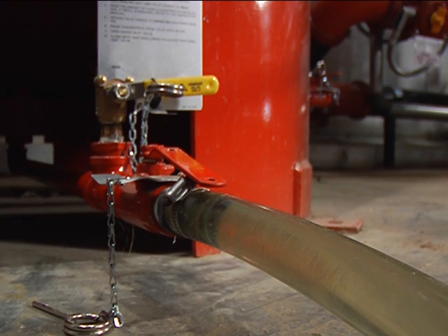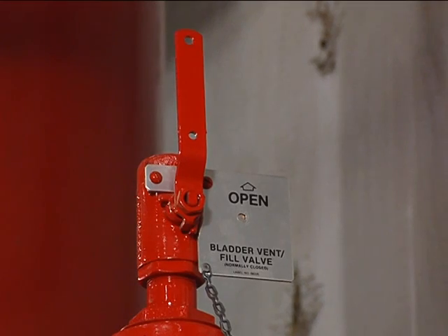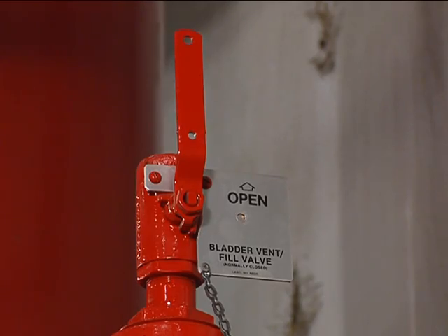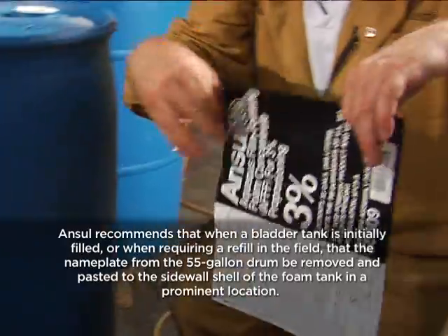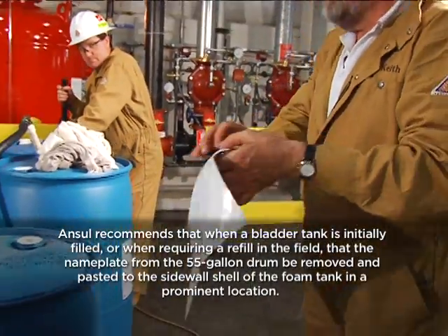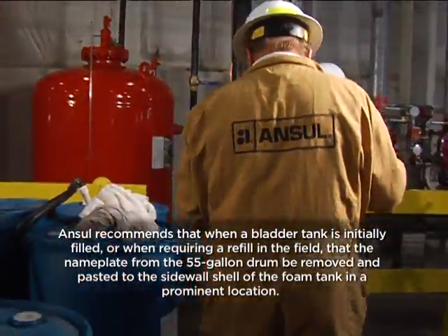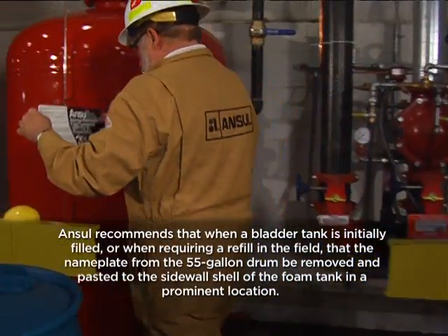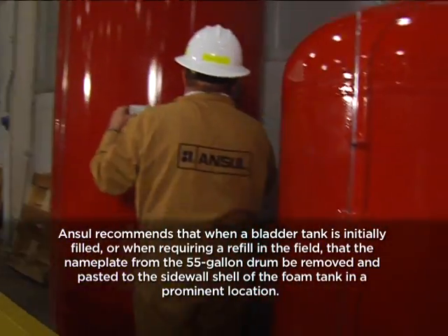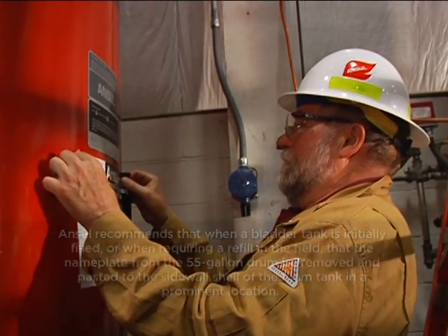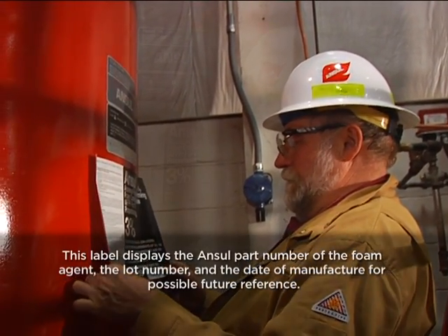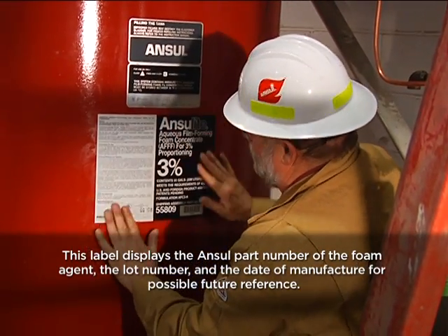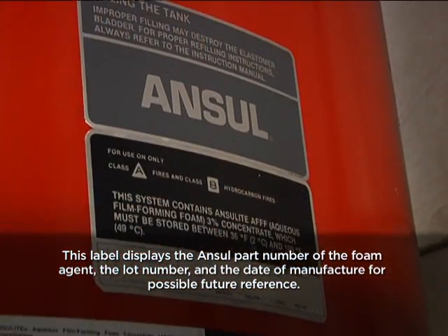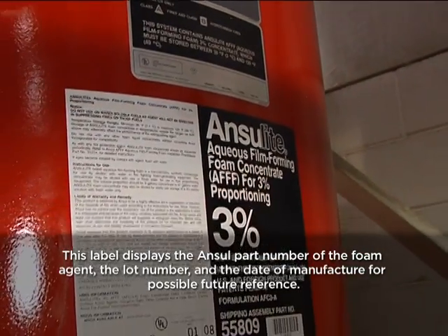At this point, the only valves that should be open are the pump valve, the bladder drain fill valve, and the bladder vent fill valve, which is venting the air being displaced by the foam concentrate. Ansul recommends that when a bladder tank is initially filled, or when requiring a refill in the field, the nameplate from the 55-gallon drum be removed and pasted to the sidewall shell of the foam tank in a prominent location. This label displays the Ansul part number of the foam agent, the lot number, and the date of manufacture for possible future reference.